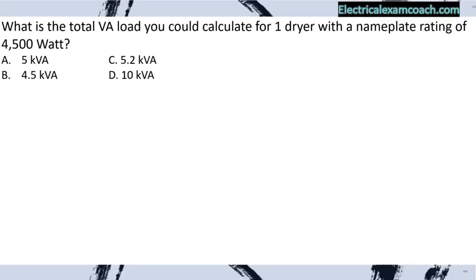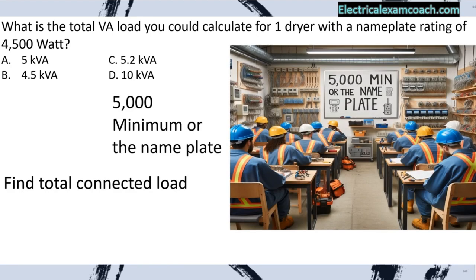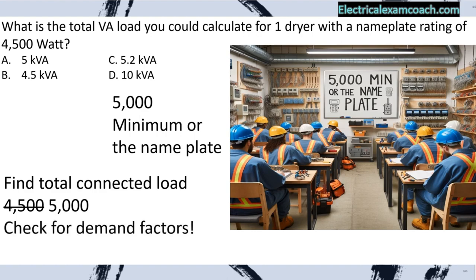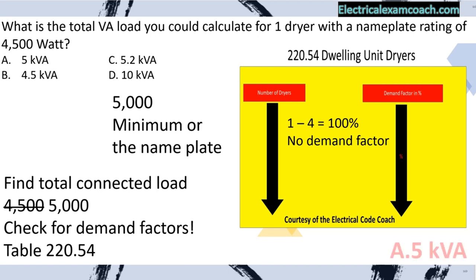Practice problem: What is the total VA load for one dryer with a nameplate rating of 4,500 watts? First, find the total connected load. We know it's 5,000 minimum or the nameplate, whichever is greater — so the 4,500 is replaced by 5,000. Check for demand factors: per Table 220.54, one through four dryers are at 100%, meaning no demand factor applies. We select A.